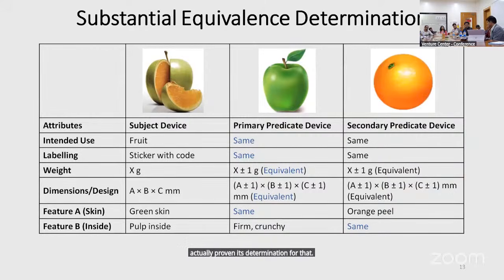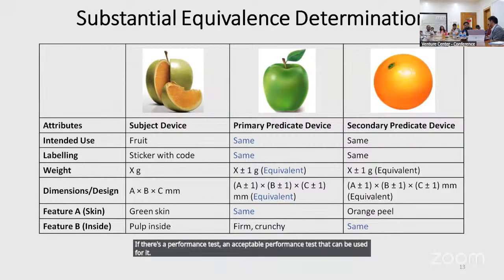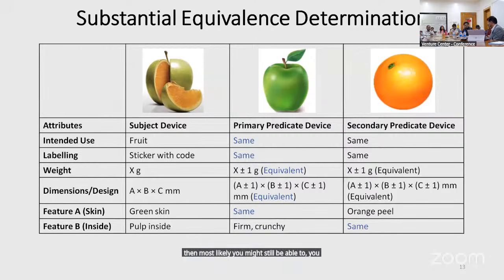Depends. If the intended use is same, primary mode of action in use is same, and if the technological characteristic differs but you can show a performance test, an acceptable performance test that can be used for it, then most likely you might still be able to go with the 510(k) route.